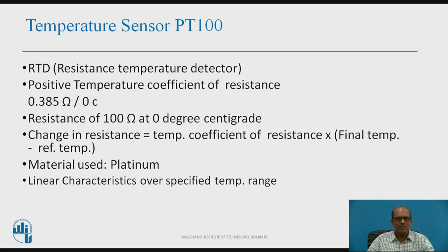Temperature Sensor PT100 is basically an RTD — RTD stands for Resistance Temperature Detector. This PT100 is made up of Platinum and it has a Positive Temperature Coefficient of Resistance. Whenever there is an increase in temperature, the resistance of PT100 increases at the rate of 0.385 ohms per degree centigrade.